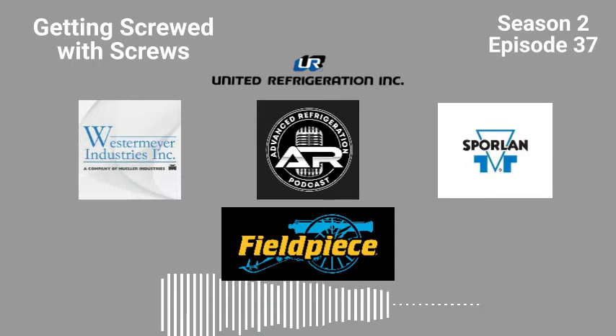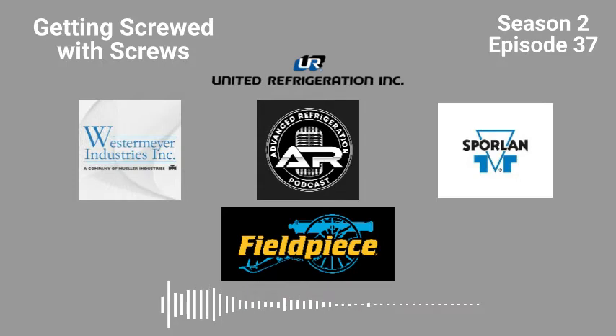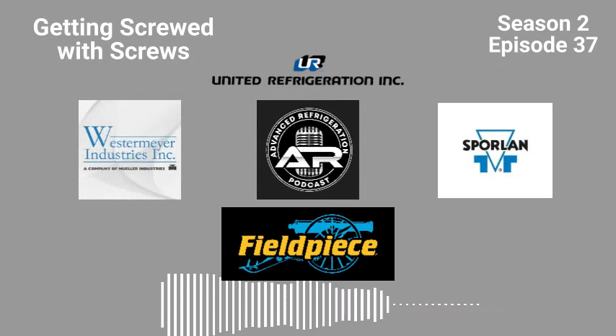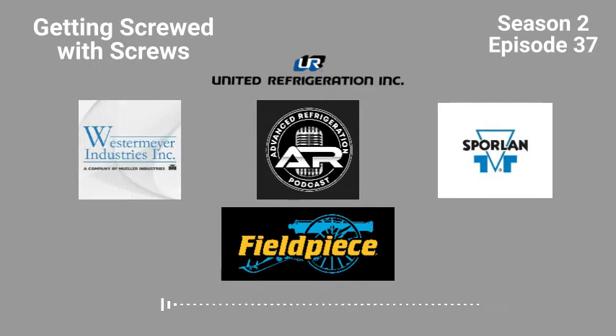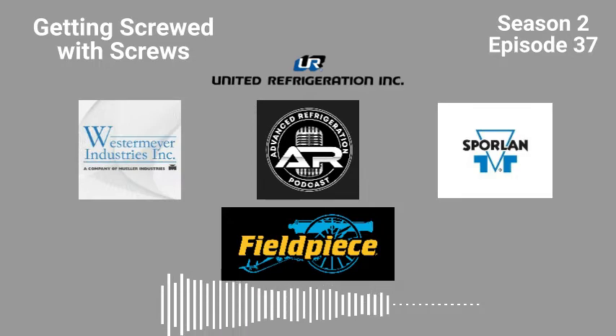I'm like, all right, let's go another quarter turn and we'll see if anything comes out. I get like an eighth of a turn in. It's probably still two more threads left. Boom! Filter blows. The housing just blows straight out, straight down, hits me in the hand, and bounces off the concrete below the rack and goes shooting back up the other way. A little bit of pressure behind it? Yeah, straight discharge pressure. That's awesome. And then the whole room just goes white.